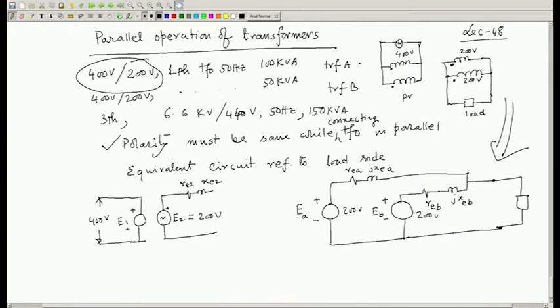In that case, if the switch is open, there will be a circulating current, which is limited by the sum of the leakage impedances of these two transformers. Anyway, people say that a little bit of difference of voltages may be allowed, provided it does not cause a large circulating current. So, although EA equal to EB is the most desirable thing, a little bit of allowance can be made, maybe it is 200, this may be 210 or so, 5-10% this way or that way. But anyway, that is why I have written EA and EB. I am not sure, they will most probably be equal and fine.